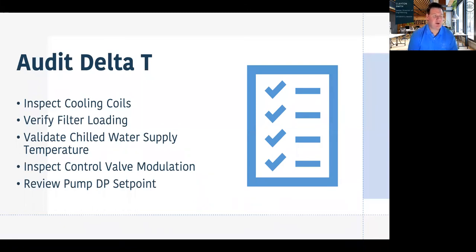Validate the chilled water supply temperature. This goes to something I preach, it feels like daily at Children's Health: we're only as good as our sensors, and our sensors are only good when they're calibrated. The smarter our building automation systems get, the more sensors we have, and the more we rely on them to be accurate. I focus a lot of attention on training plant operators to have a sensor on the shelf, ready to show up with that sensor and test it first. Usually, when we get into these situations, we'll break down a whole system trying to figure out what the problem is, and it's a bad sensor. So keep those sensors calibrated, keep them tight, and trust the information you have because you've verified and validated your sensors.